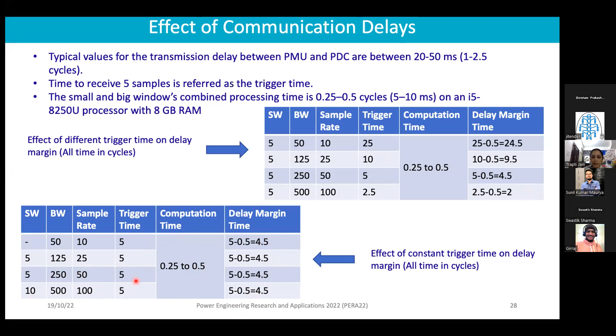Now, how to decide the threshold? That's another important question that needs to be answered. We analyzed different archived data for events and found there is a positive correlation between the variability of a small window and change in frequency. Usually for a fast event, the change in frequency will vary from 0.03 hertz to 0.25 hertz, depending on the severity of the event.